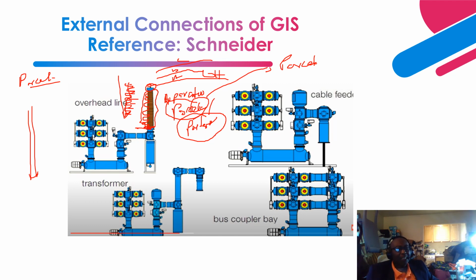Porcelain has a lower hydrophobicity. So hydrophobicity, what does that mean? That is an industry technical word for a phenomenon. It means that it doesn't have the capability to repel contaminants. If you have this type of bushing located in an environment with an industrial facility, oil contaminant, dust contaminant, sandy contaminant, salty contaminant, all of them are going to form on the surface. This porcelain does not have that capability to repel them, so all the contaminants are going to form on the surface. With a lot of raindrops, you then have a leakage current flowing, and it can cause a flashover. So that is one of the disadvantages or drawbacks of this type of bushing.